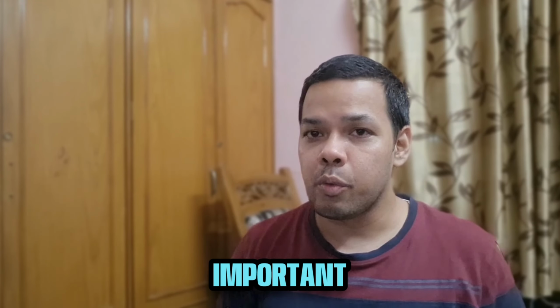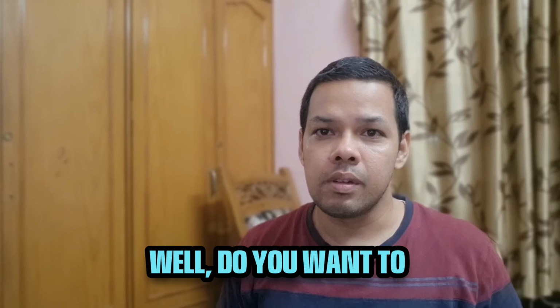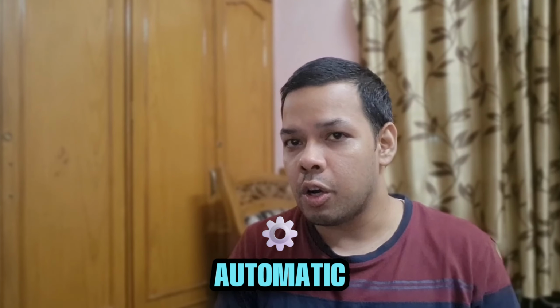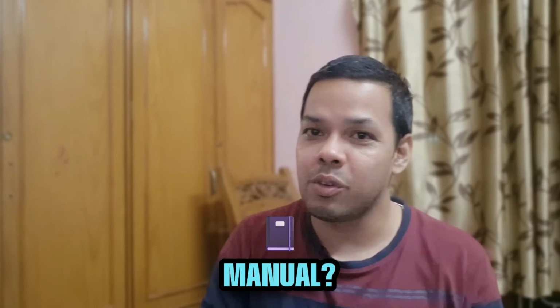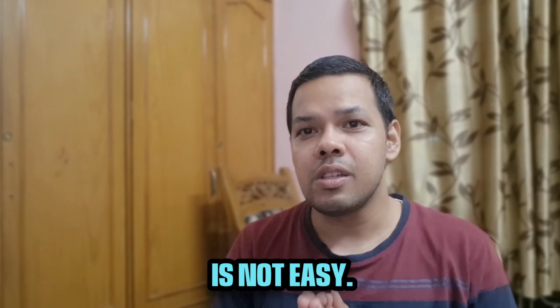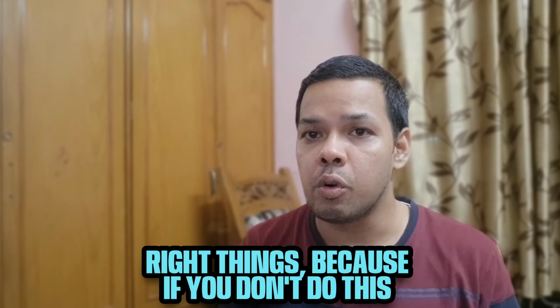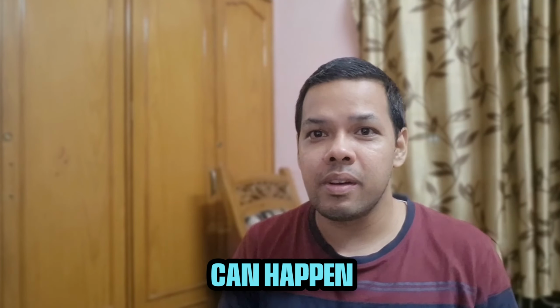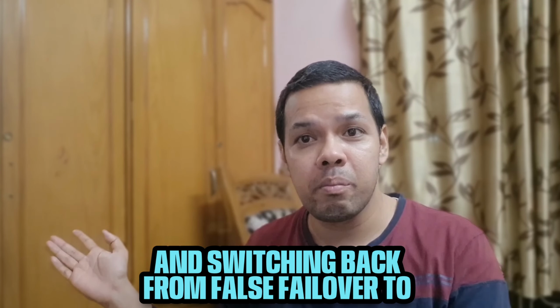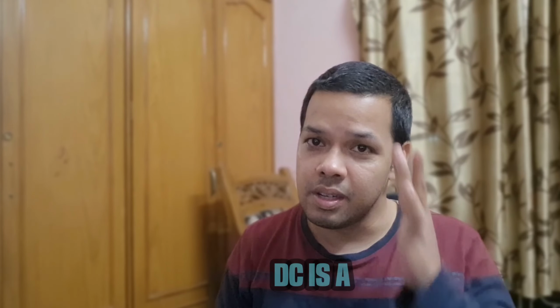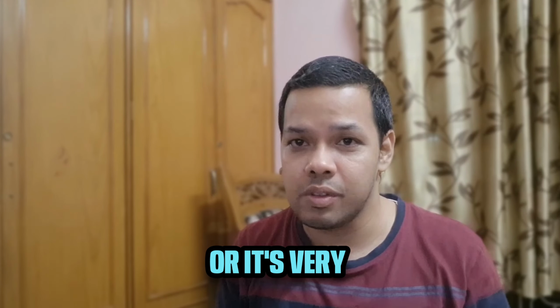Now comes the important question. Do you want to do it automatic or do you want to do it manual, right? So automatic is not easy. You have to configure a lot of things right, because if you don't do this right, false failures can happen, and switching back from a false failover to DC is a headache, very complicated.